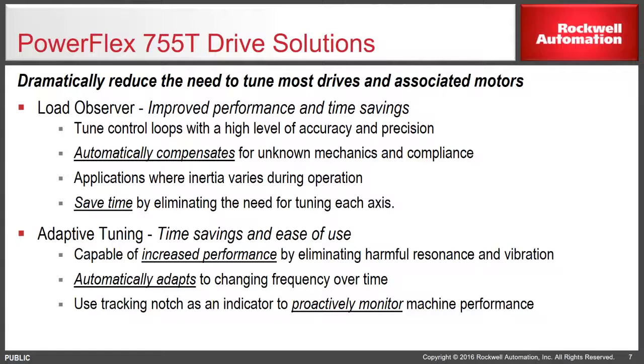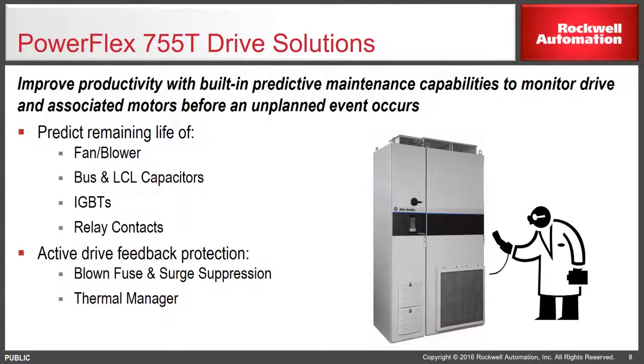Adaptive tuning is capable of increased performance by eliminating harmful resonance and vibration. Automatically adapts to changing frequency over time. Use tracking notch filter as an indicator to proactively monitor machine performance. Improve productivity with built-in predictive maintenance capabilities to monitor drive and associated motors before an unplanned event occurs.